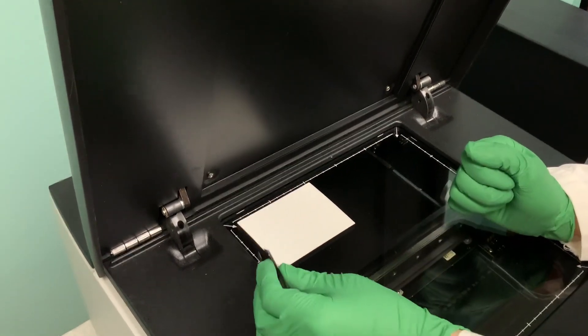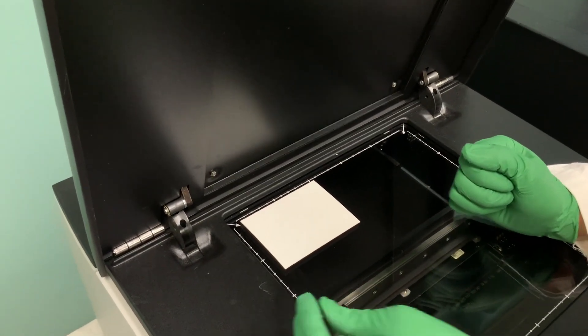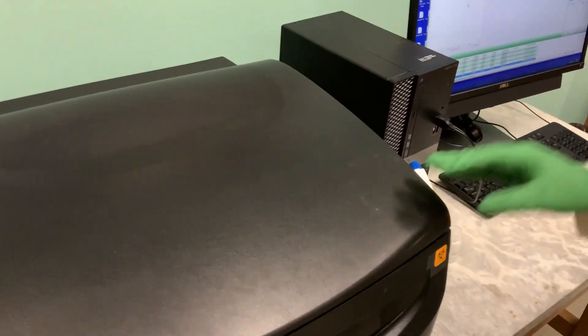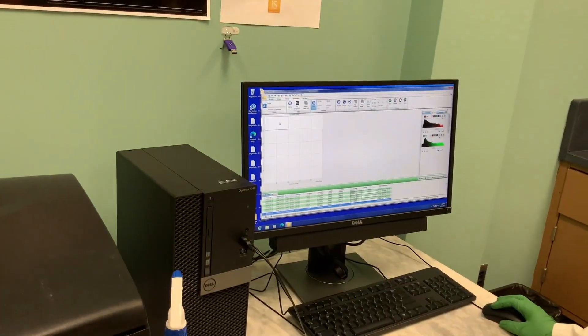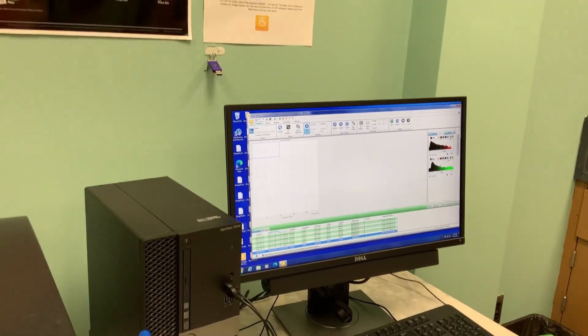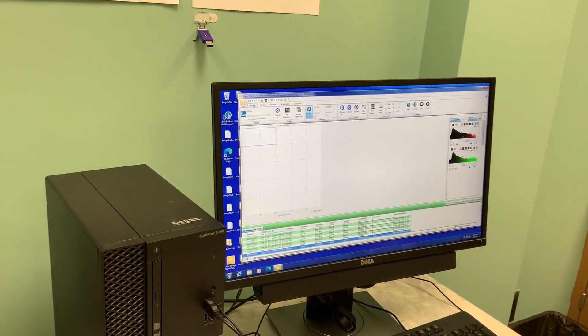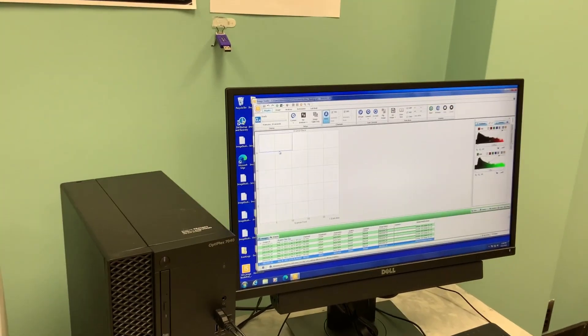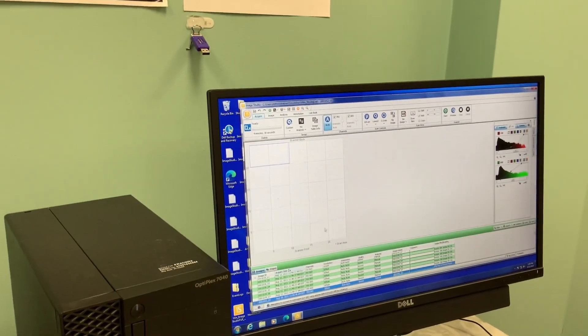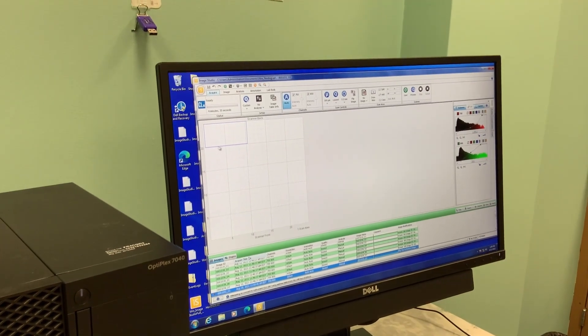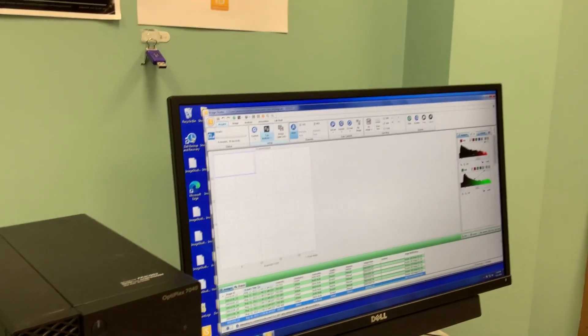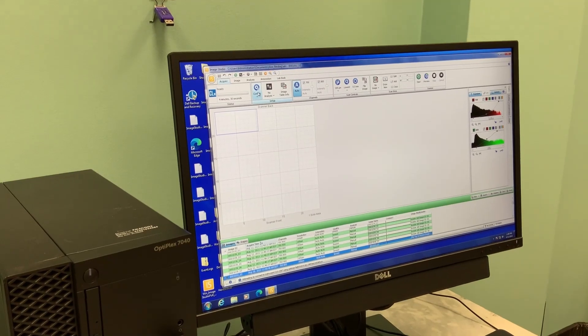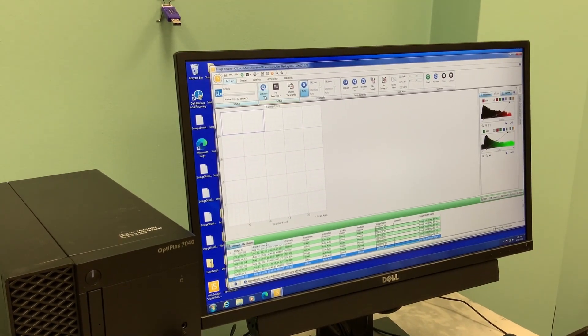We're going from the first tick of each one, going out two major ticks and then one and a half major ticks in the bottom direction. We need to know that because then we come here and under the Acquire tab we draw the size of the area that we need to scan.